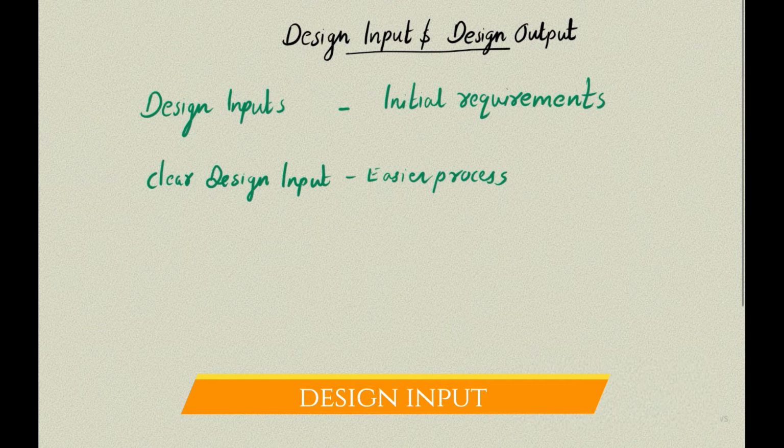So the company should establish and maintain a procedure to ensure that the design inputs related to the device are appropriate and address all the intended use of the device, and also address the needs of the user and the patient. So for this, the design input shall be effectively documented and also shall be reviewed and approved by designated individuals and follow a systematic, well defined process so that the end product you are getting will have better quality and safety features.